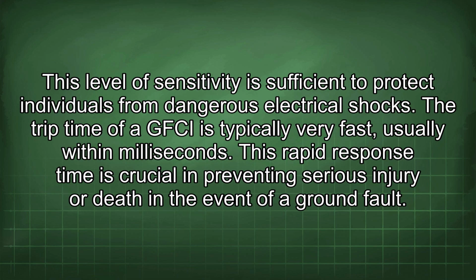This level of sensitivity is sufficient to protect individuals from dangerous electrical shocks. The trip time of a GFCI is typically very fast, usually within milliseconds. This rapid response time is crucial in preventing serious injury or death in the event of a ground fault.